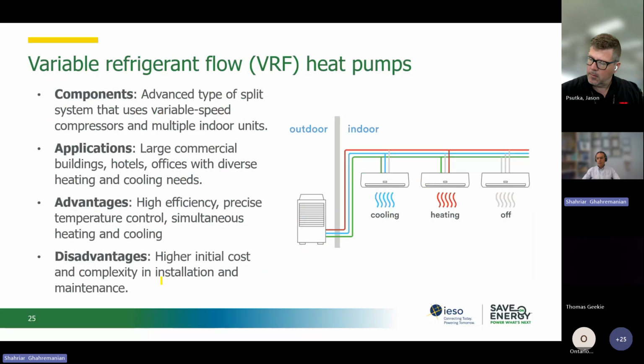The next one that I want to expand on a little bit is the variable refrigerant flow heat pumps actually. Variable refrigerant flow heat pumps are similar to air source heat pumps, which means that they use outdoor air as a source, but inside, instead of ducts for the air or water pipes for the hydronic system, we just distribute the refrigerant through the pipes. And the good thing is that these systems are very advanced types of split systems, ductless split systems, and they're good for large commercial buildings, hotels, offices, with diverse heating and cooling needs. So if one area requires heating and the other area requires cooling, these VRF systems can work in those situations, and they are really good actually.